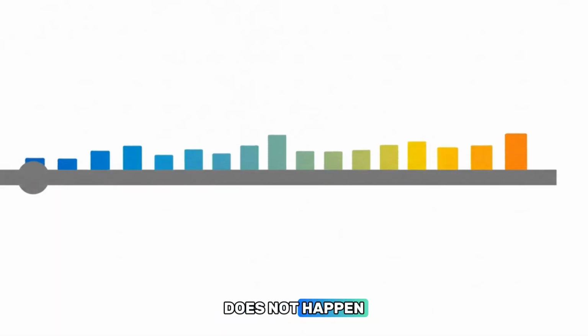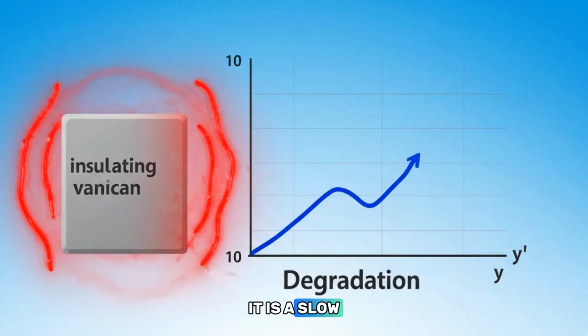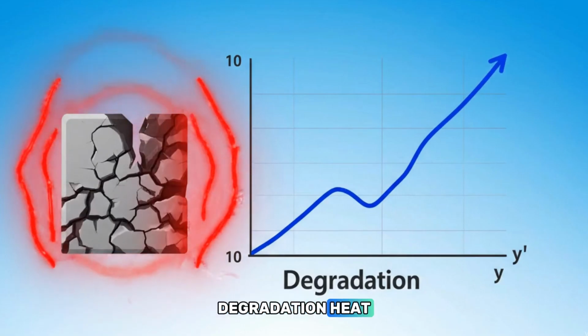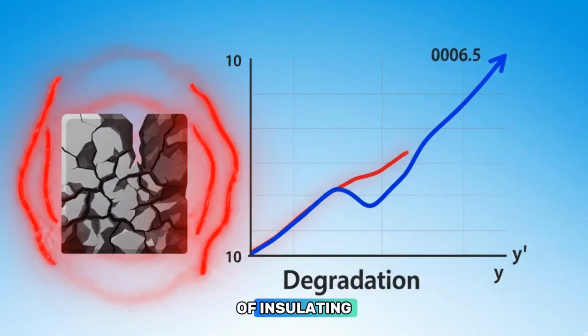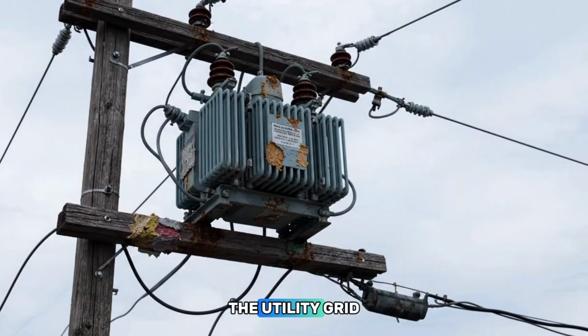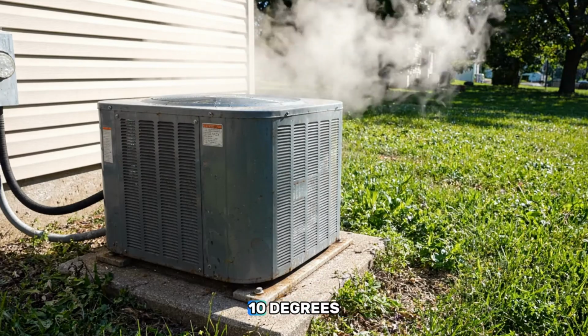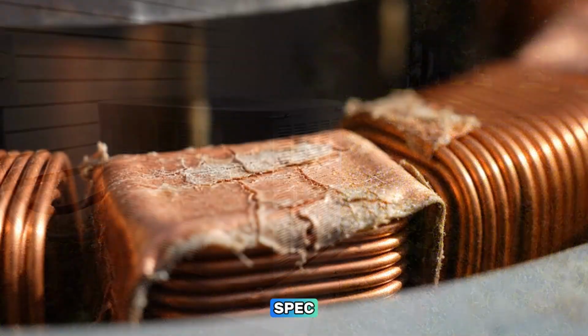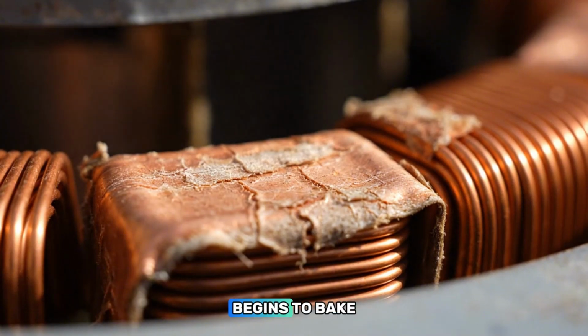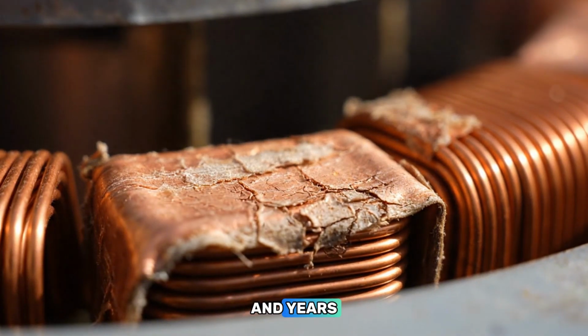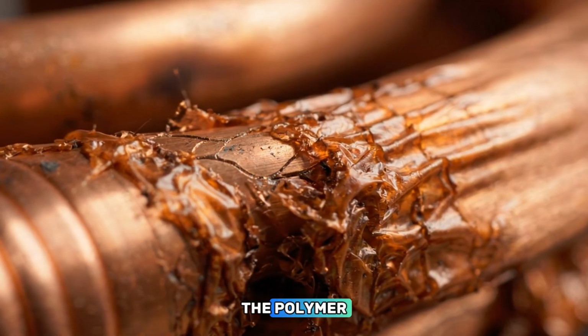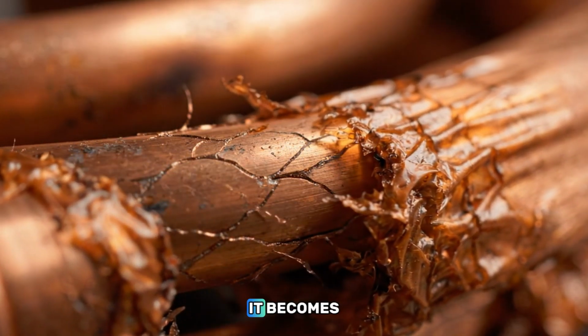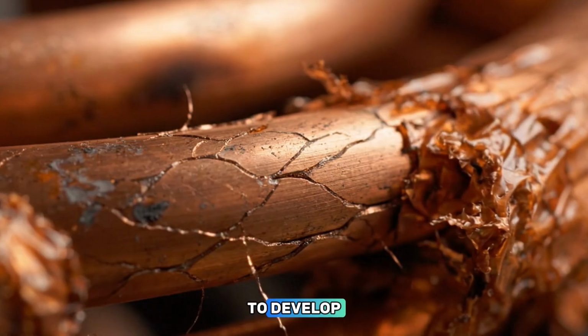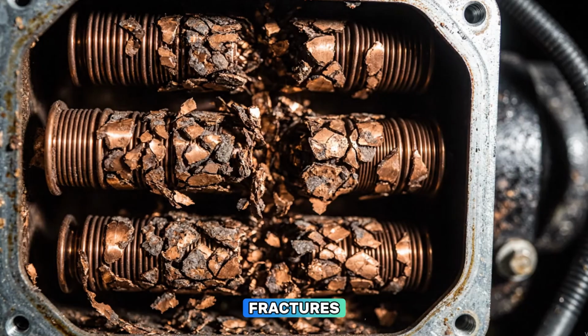The failure does not happen overnight. It is a slow, methodical degradation. Heat is the absolute enemy of insulating varnish. Every time the utility grid forces your compressor to run 10 degrees hotter than its design spec, the microscopic varnish layer begins to bake. Over months and years of these silent brownouts, the polymer loses its elasticity. It becomes brittle. It begins to develop microscopic hairline fractures.